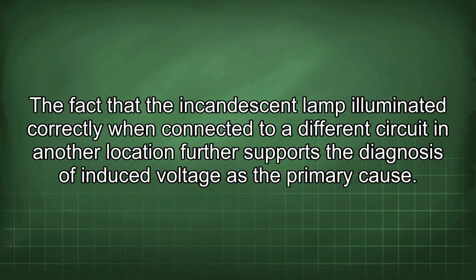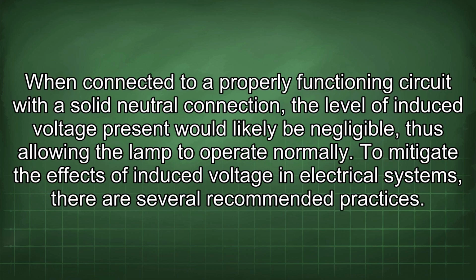The fact that the incandescent lamp illuminated correctly when connected to a different circuit in another location further supports the diagnosis of induced voltage as the primary cause. When connected to a properly functioning circuit with a solid neutral connection, the level of induced voltage present would likely be negligible, thus allowing the lamp to operate normally.